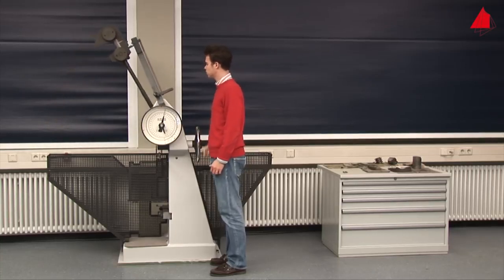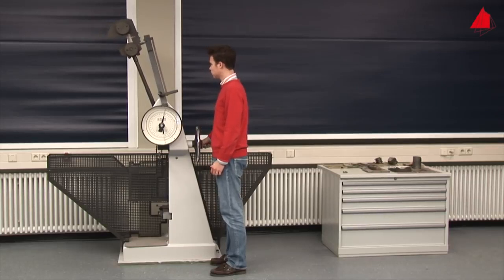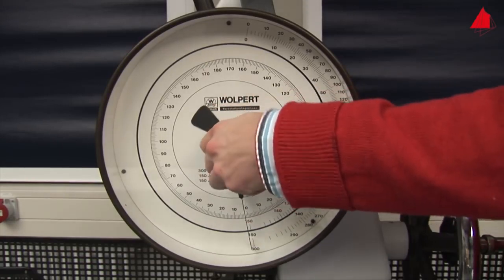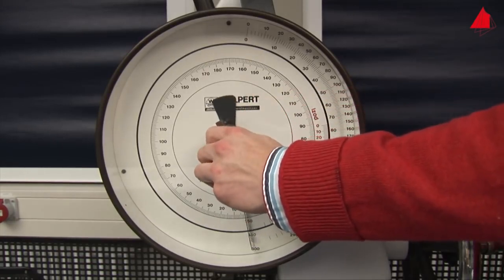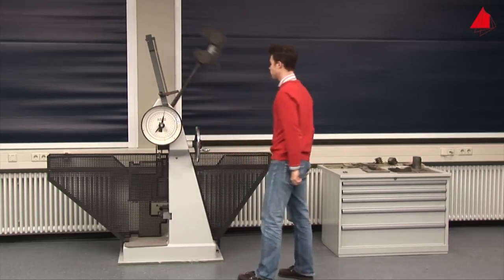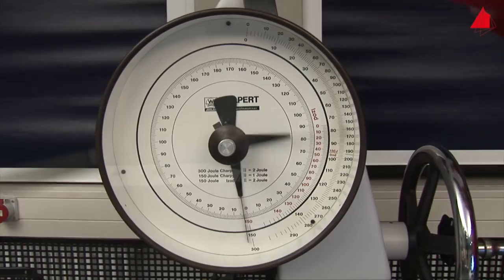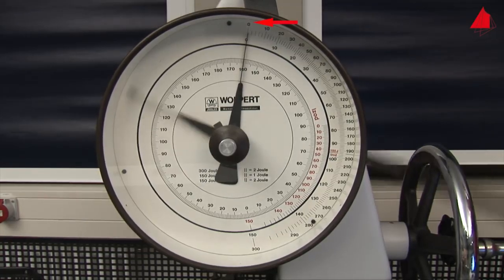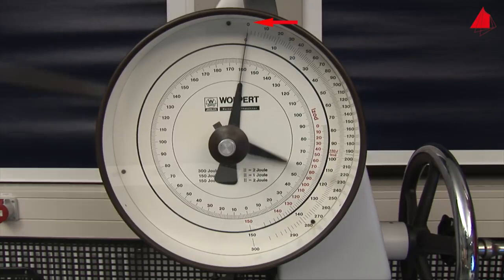Then the tester checks whether the testing machine has been adjusted accurately. In order to do this he turns the drag indicator downwards and releases the pendulum without a test specimen. The drag indicator stops at position zero. This proves that the pendulum has the correct starting position and that the friction is correctly compensated.